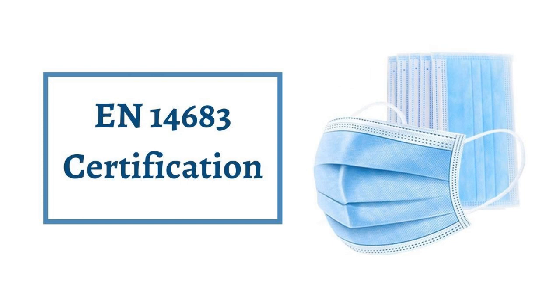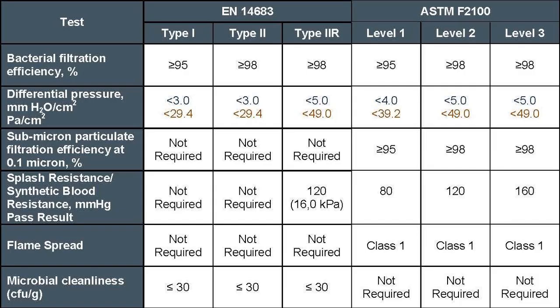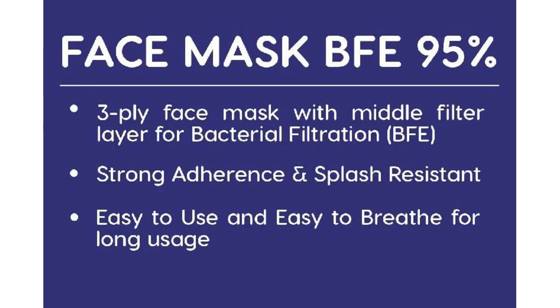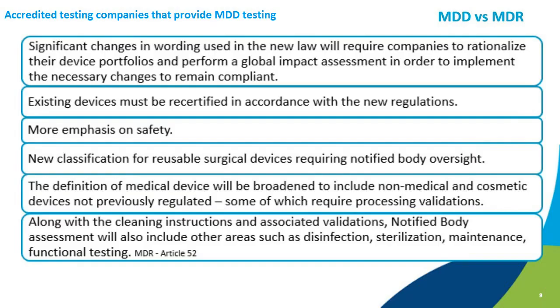EN 14683 Harmonized Standard. The EN 14683, Medical Face Masks, is a harmonized standard under the MDD and provides requirements and test methods for medical face masks. In general, the EN 14683 standard classifies the masks into 3 categories based on their performance. R indicates that the mask offers protection for liquid splash, while other performances such as BFE remain the same. Testing companies. There are several accredited testing companies that provide MDD testing services for face mask products.